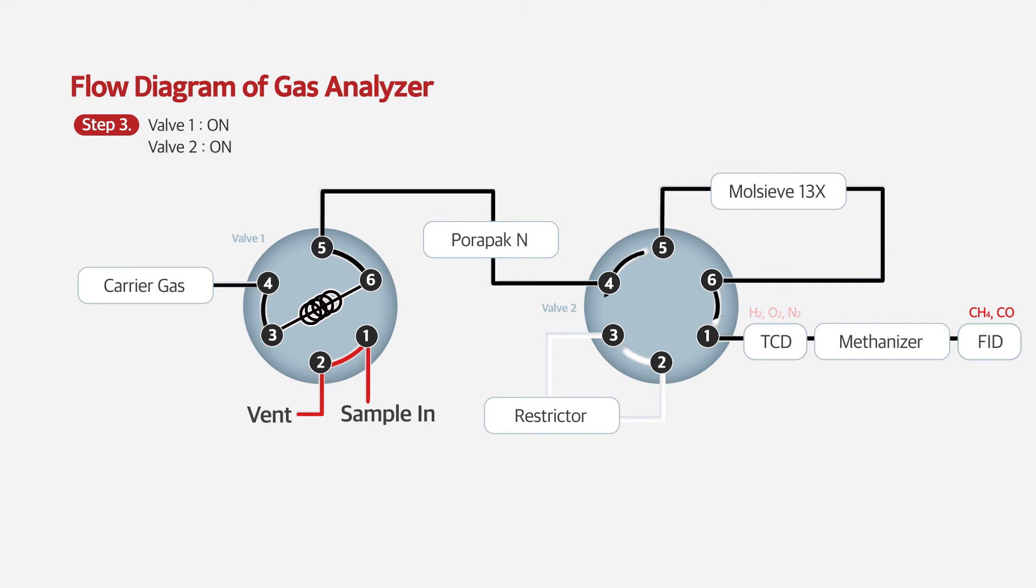After valve two is on, heavy gases such as carbon dioxide to propane are separated in Porapak N column and detected by FID. Among these gases, carbon dioxide is converted to methane in the methanizer and then detected.